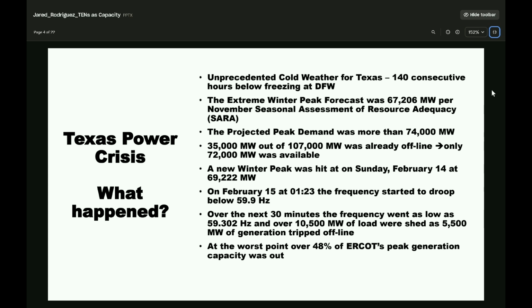So what happened exactly? In simple terms, the demand exceeded the supply. There are more air source heat pumps in Texas, as a proportion of total heating systems, than almost any other place in the country. Did you know that? And they're not really designed to operate at very low temperatures, below 20 degrees Fahrenheit. So what happens is they go from being fairly efficient in the 35 to 40 degree range to not being efficient at all - their coefficient of performance degrades significantly as the temperature drops toward zero.